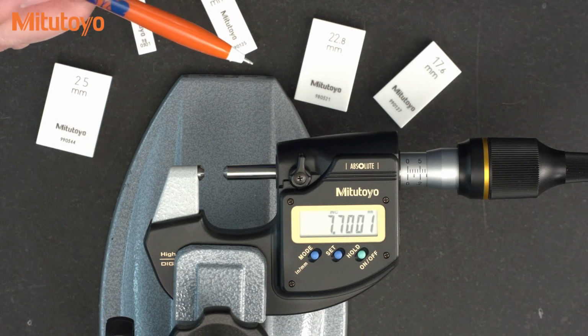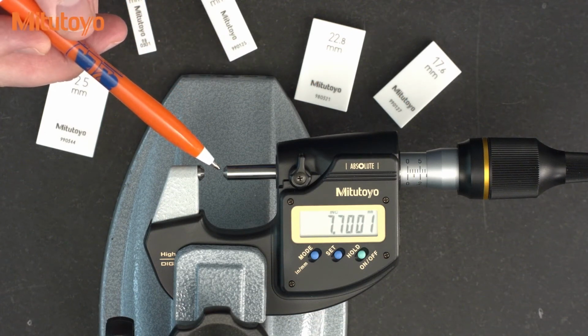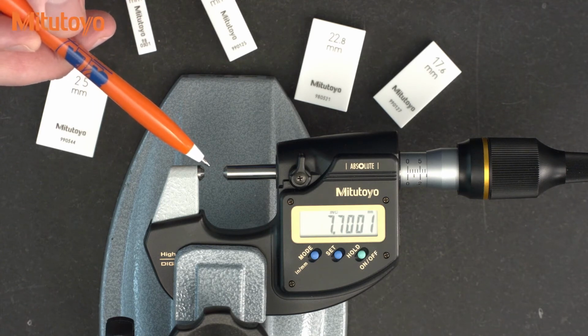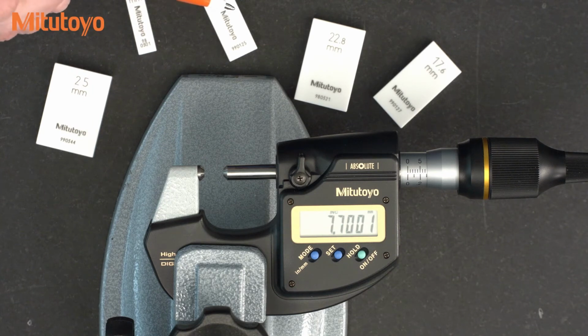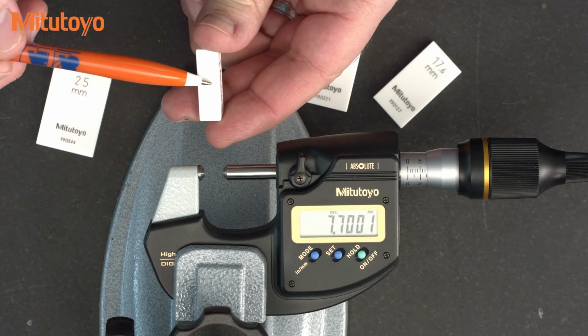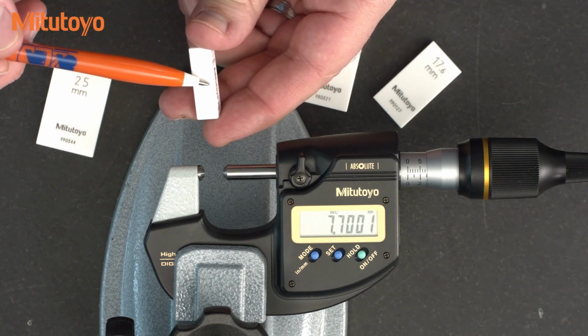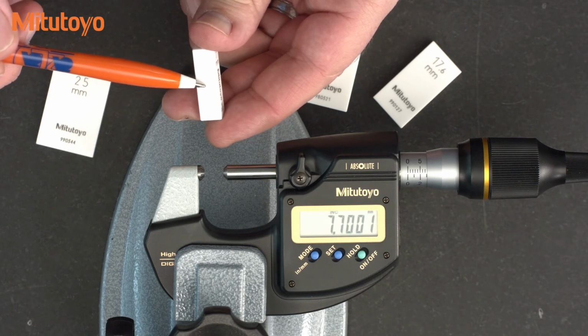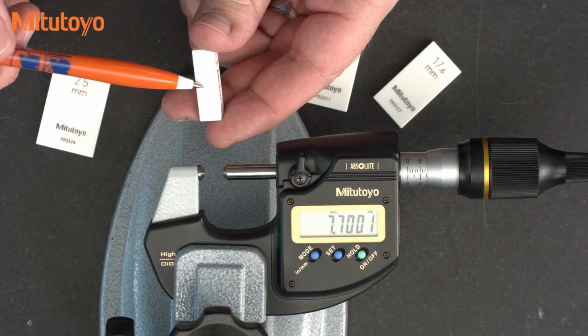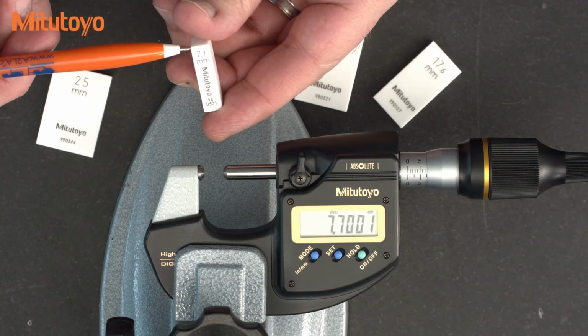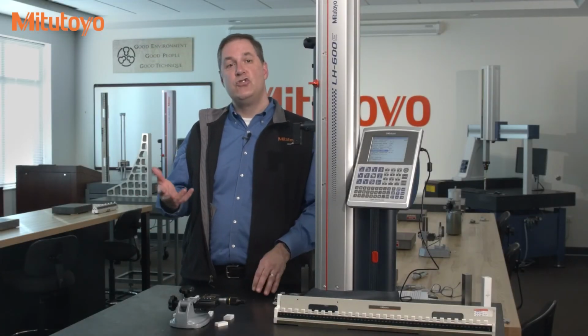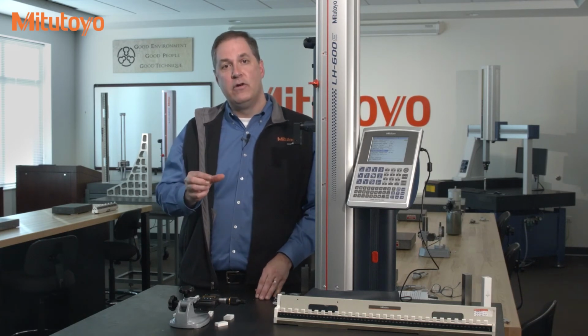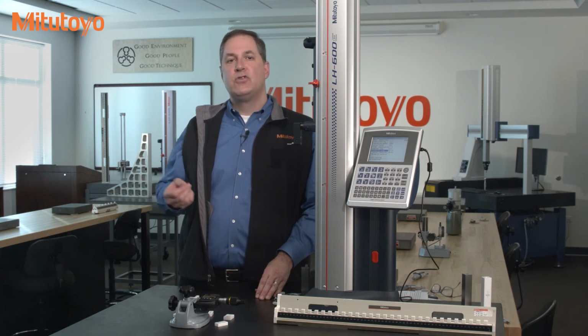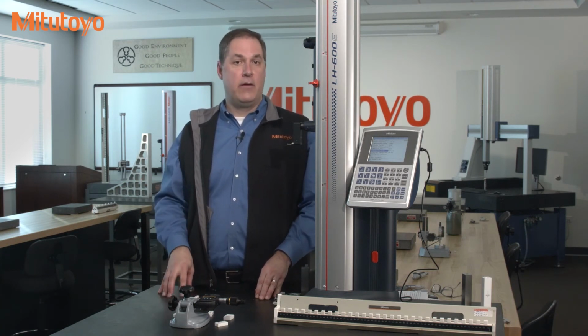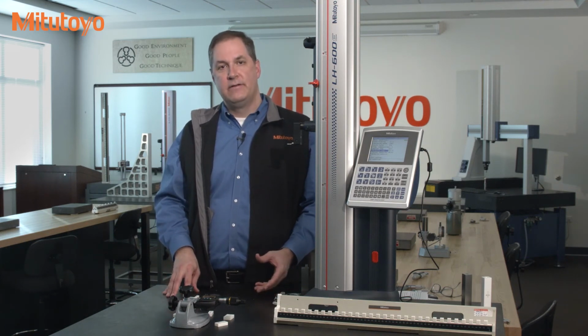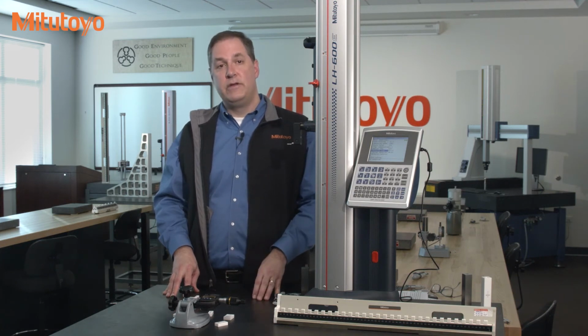If you look at the MDH, you'll notice that the measuring faces are about half the diameter of most other micrometers. We realized we could take advantage of this and measure the gauge blocks at the central gauging point. This point has a calibrated value given on the calibration certificate, and using this calibrated value is generally much more accurate than using the nominal value that's marked on the gauge block. So that's the second solution. Just use the calibrated value, not the nominal value for the gauge blocks you already own. So we started implementing that process here at Mitutoyo America in our calibration lab when we realized something about our gauge blocks, which led to a third solution, which is the one that we use today.